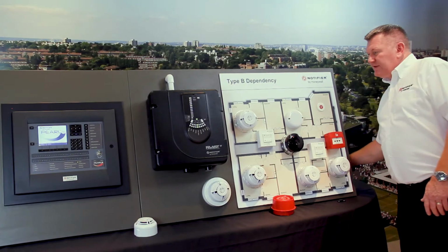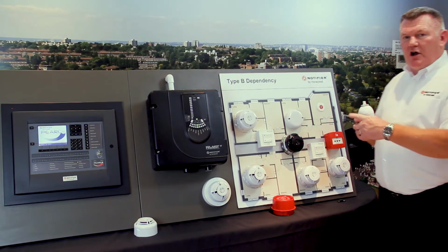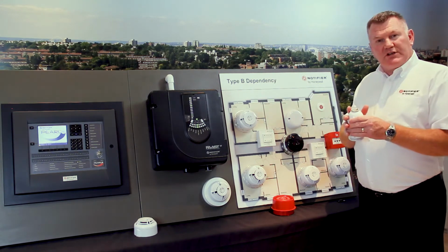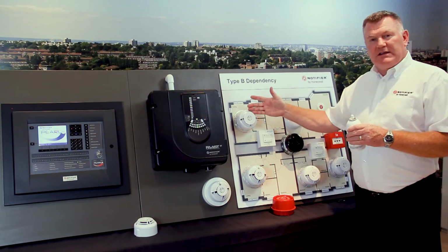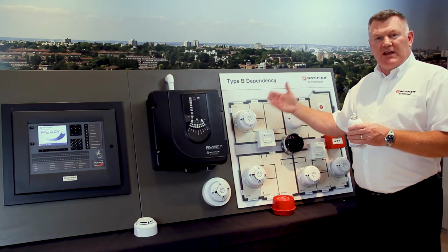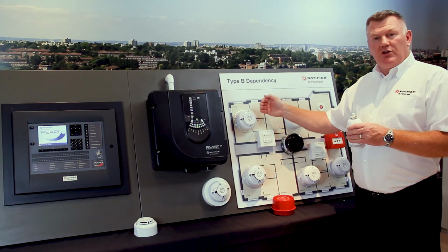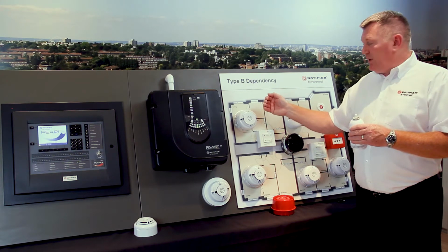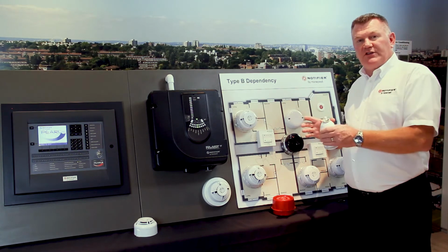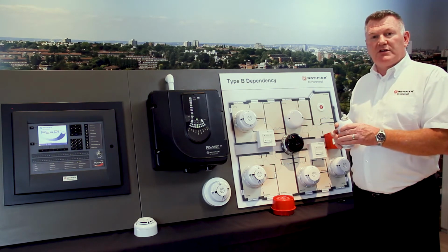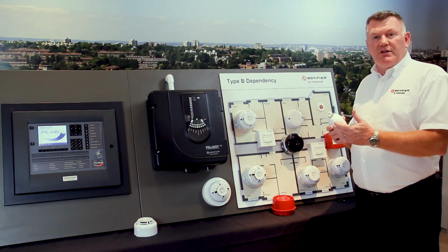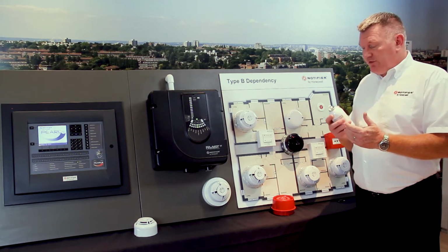So what I want to do this time is do the same scenario again. So flat 1 with some smoke this time. I'll put some smoke into the detector chamber, but I'll keep adding some smoke to make sure the smoke stays in the detector chamber until we come to the end of the confirmed period. The way we've set the system up is we've set it up for a 30-second confirmation time period. Normally that confirmation period would be 2-3 minutes, not as short as 30 seconds.